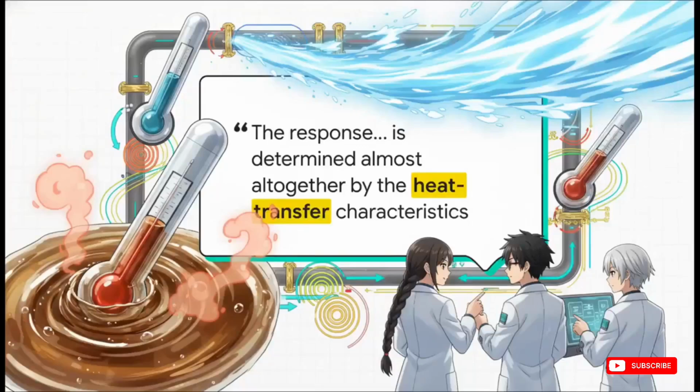And finally, here is a massive pro tip for when you're actually out in the field. Always remember this rule of thumb. Your thermometer is only as fast as the heat transfer allows. The response time isn't just about the dial, it's dictated by the thermal capacitance, the thermal conductivity, and the film coefficients of the fluid surrounding the bulb. Basically, if you stick a thermometer in a slow-moving, thick oil, it's going to respond much, much slower than if it were sitting in high-velocity steam.